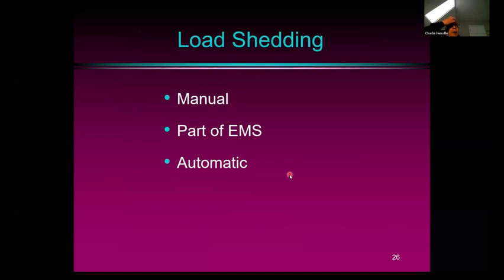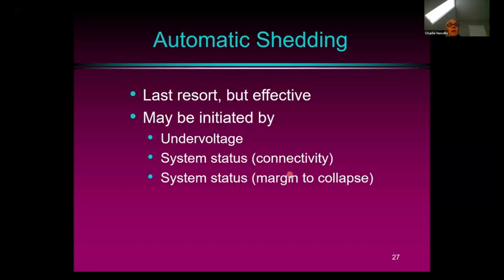And in the worst case, you may get to load shedding, which is that scheme I showed you earlier on, where you really don't want to shed firm load unless you have to, unless your system's in extreme trouble. So you can use manual load shedding or the energy management system, or some sort of automatic scheme. And it's a last resort, but sometimes required. And you may use undervoltage, system status, or the margin to collapse. So all of these things are different techniques to initiate load shedding to prevent blackout.